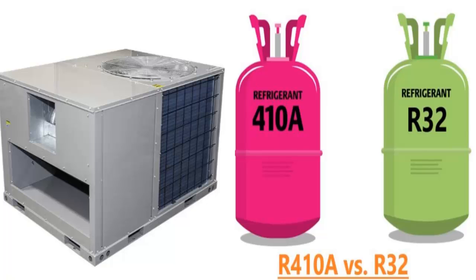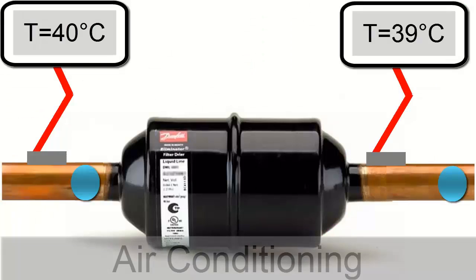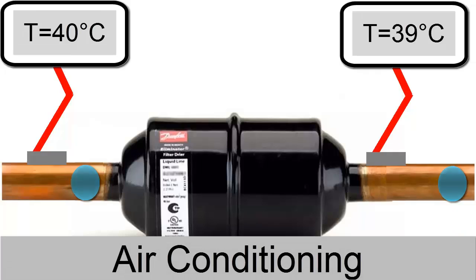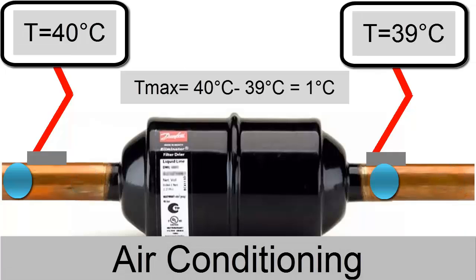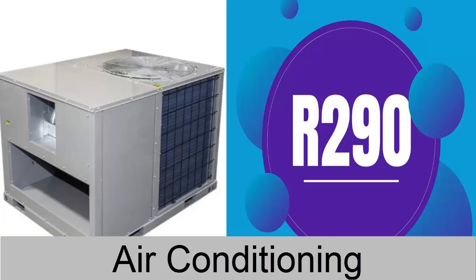For air conditioning, with R-410A and R-32 gases, the temperature drop indicating obstruction is 1 degree Celsius. With R-290, it's 1.5 degrees Celsius.